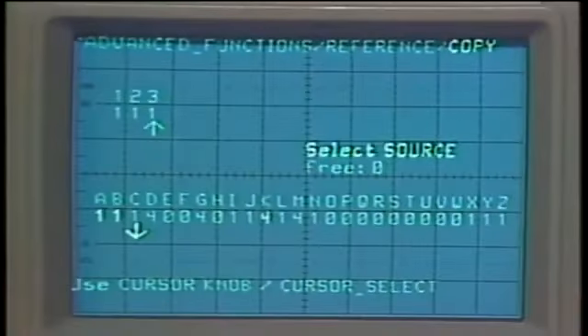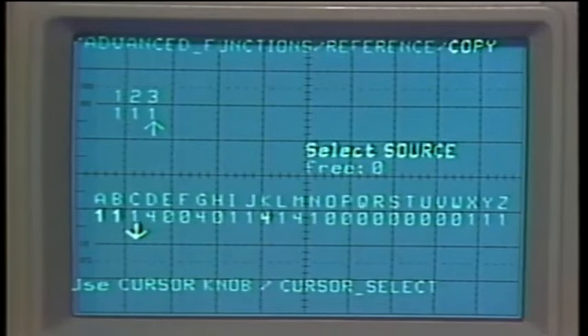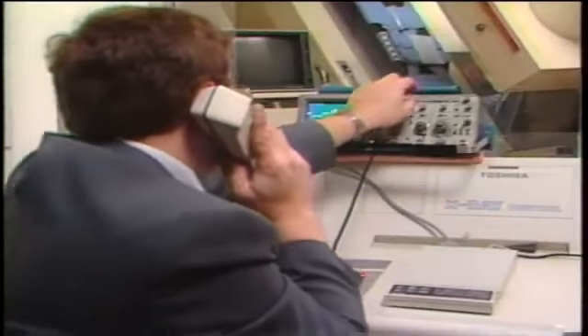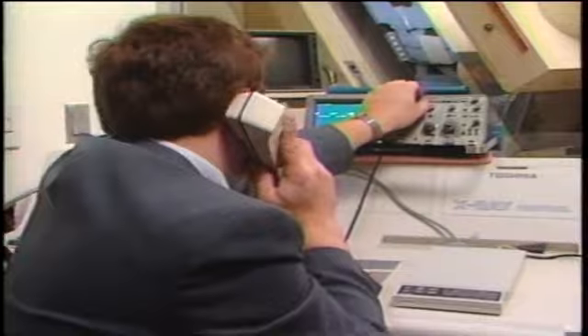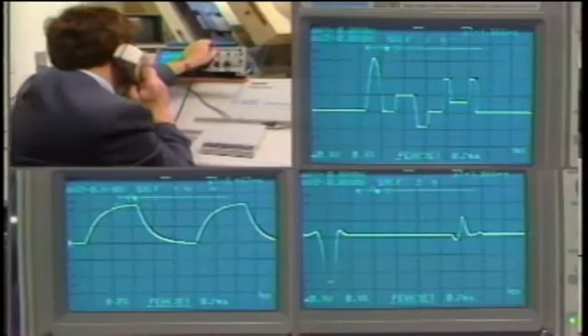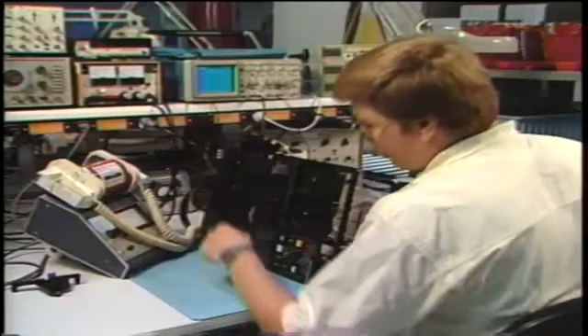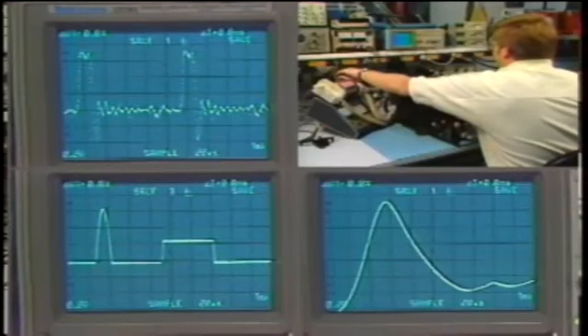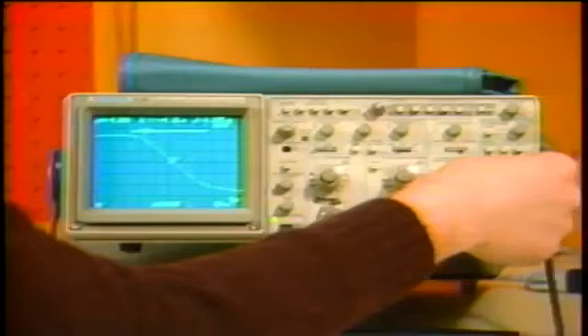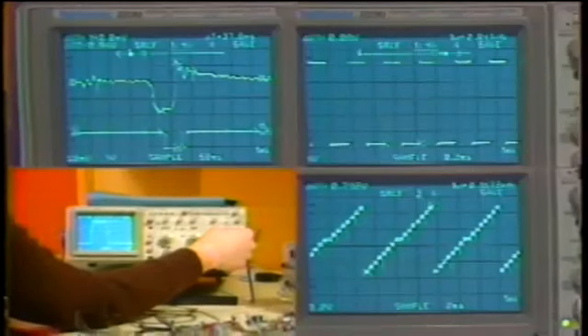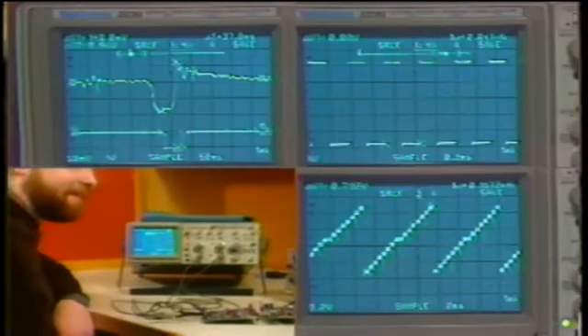Do you need to build a reference waveform library? The 2230 includes an expanded waveform memory in the communications options. This can store up to 26 waveforms in battery-backed memory for up to 3 years. A service or biomedical equipment technician would store troubleshooting or calibration waveforms. In manufacturing test, the extended waveform memory might be used to store repetitive test comparison waveforms. A design engineer would compare waveform changes with design changes.